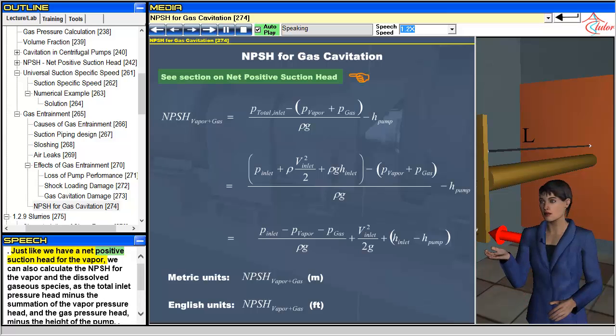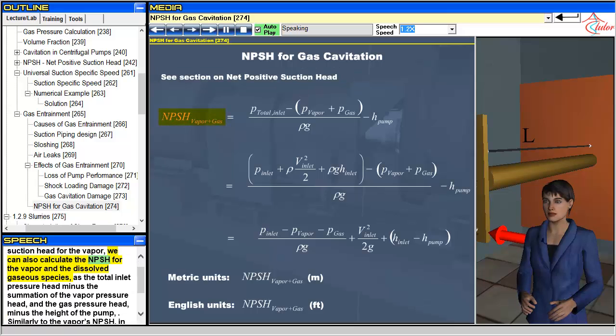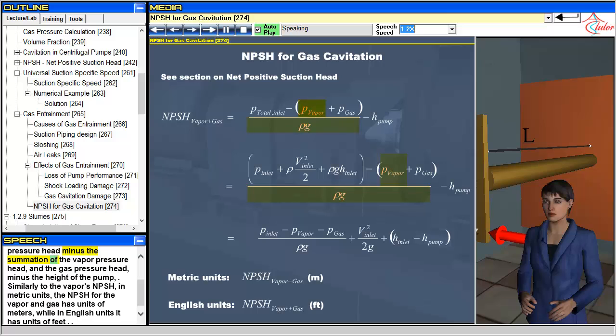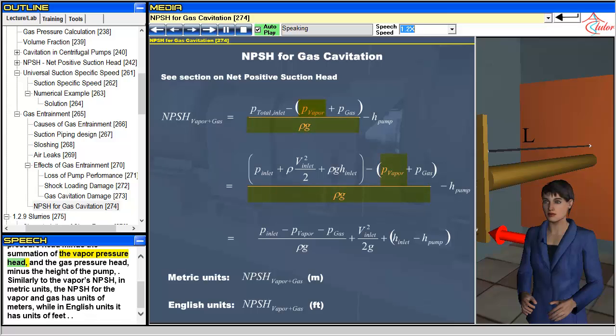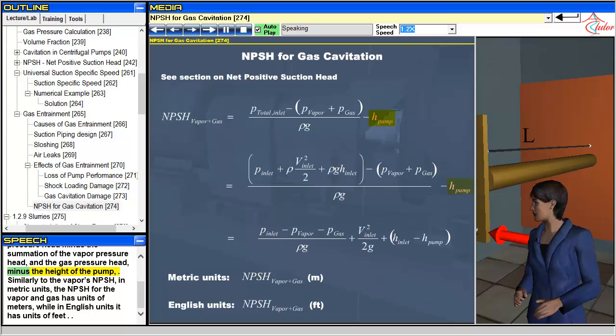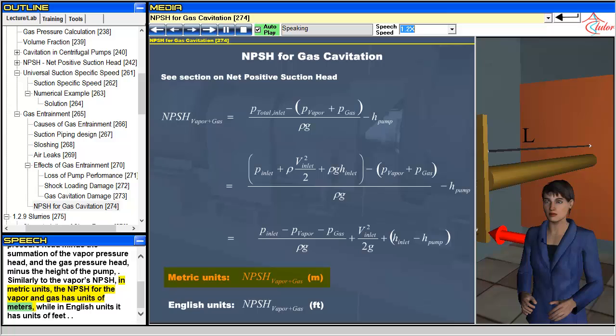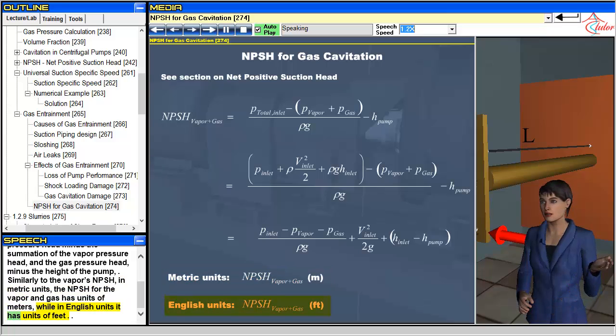Just like we have a net positive suction head for the vapor, we can also calculate the NPSH for the vapor and the dissolved gaseous species as the total inlet pressure head minus the summation of the vapor pressure head and the gas pressure head minus the height of the pump. Similarly to the vapor's NPSH, in metric units the NPSH for the vapor and gas has units of meters, while in English units it has units of feet.